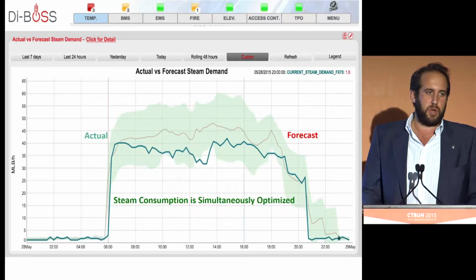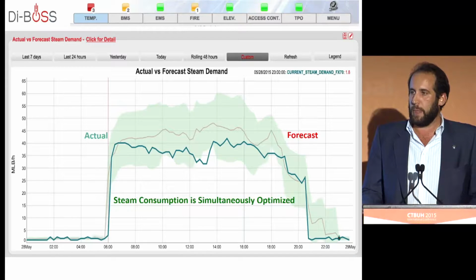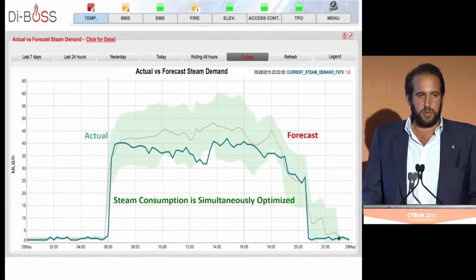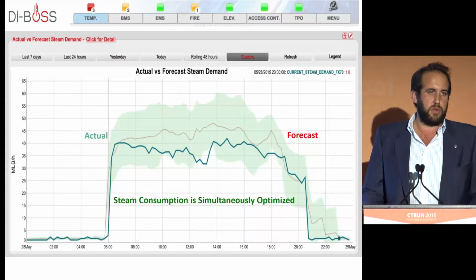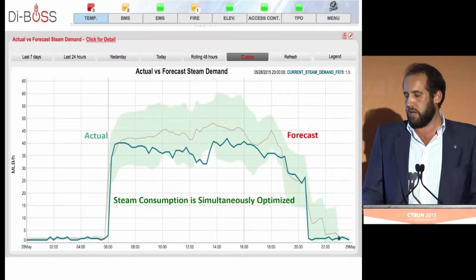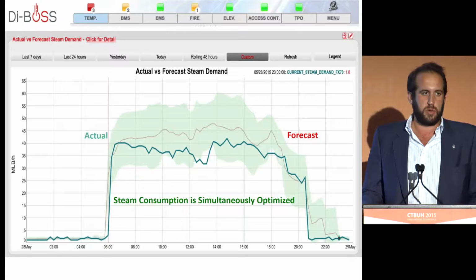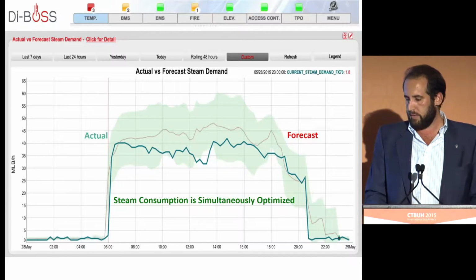So we've shaved our operational days, something discussed earlier. Shaving the operational day on a yearly basis has resulted in huge savings across our portfolio, reducing that ramp down time in the afternoon to a more precise time of day, as opposed to the historical information our building engineers and operators were going off of.